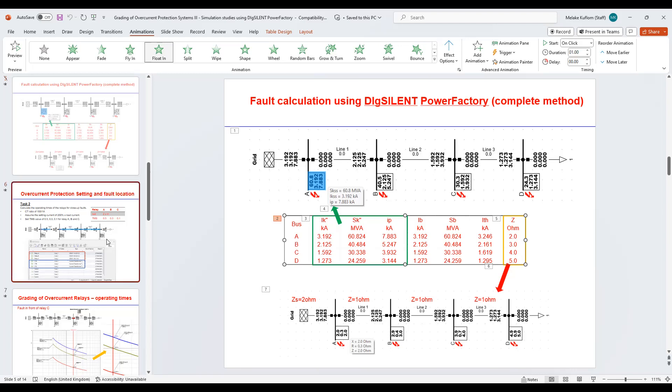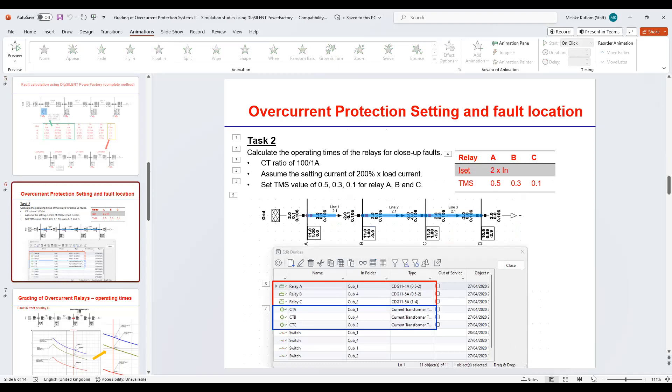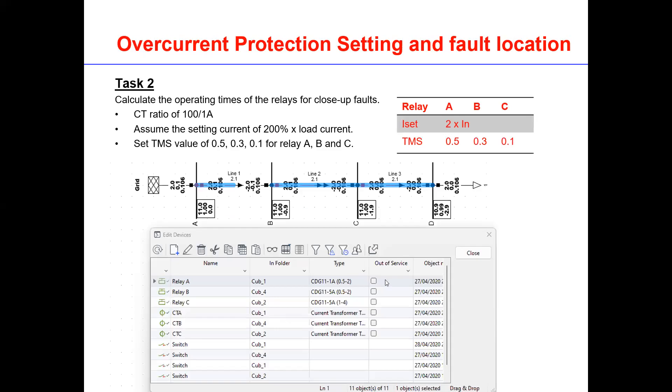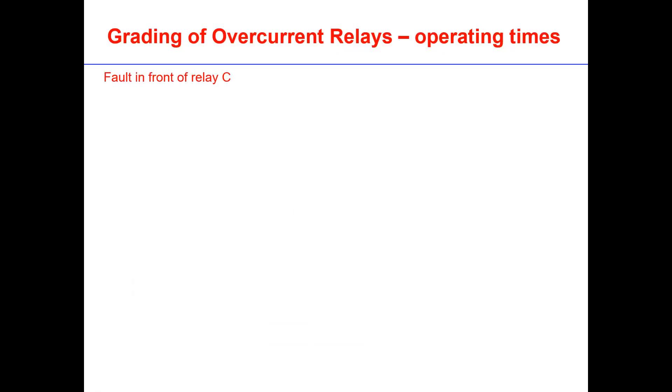From that, we can do the next step, which is the relay setting calculations, which is classical. We need to calculate the operating times of the relay for close-up faults, just when fault is in front of the relay. We need to consider the setting current is 2 times the loading current. And then of course add different TMS for each relay. If we look at here, the TMS is 0.5 for relay A, and then relay B is 0.3, and relay C is 0.1. And then of course this is just configured in DIgSILENT. This is relay A, B, C, and CTA, B, C for transformers.